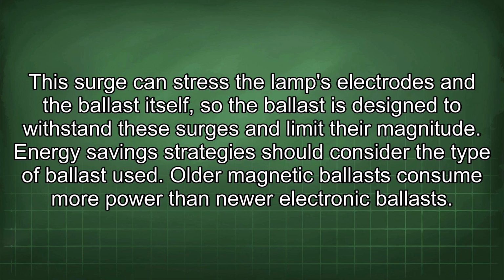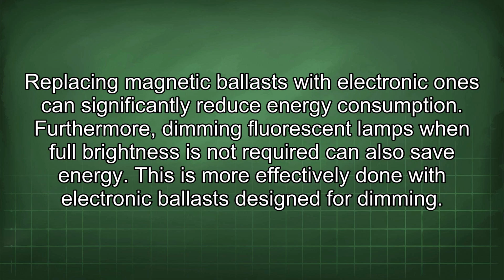Older magnetic ballasts consume more power than new electronic ballasts. Replacing magnetic ballasts with electronic ones can significantly reduce energy consumption. Furthermore, dimming fluorescent lamps when full brightness is not required can also save energy. This is more effectively done with electronic ballasts designed for dimming.